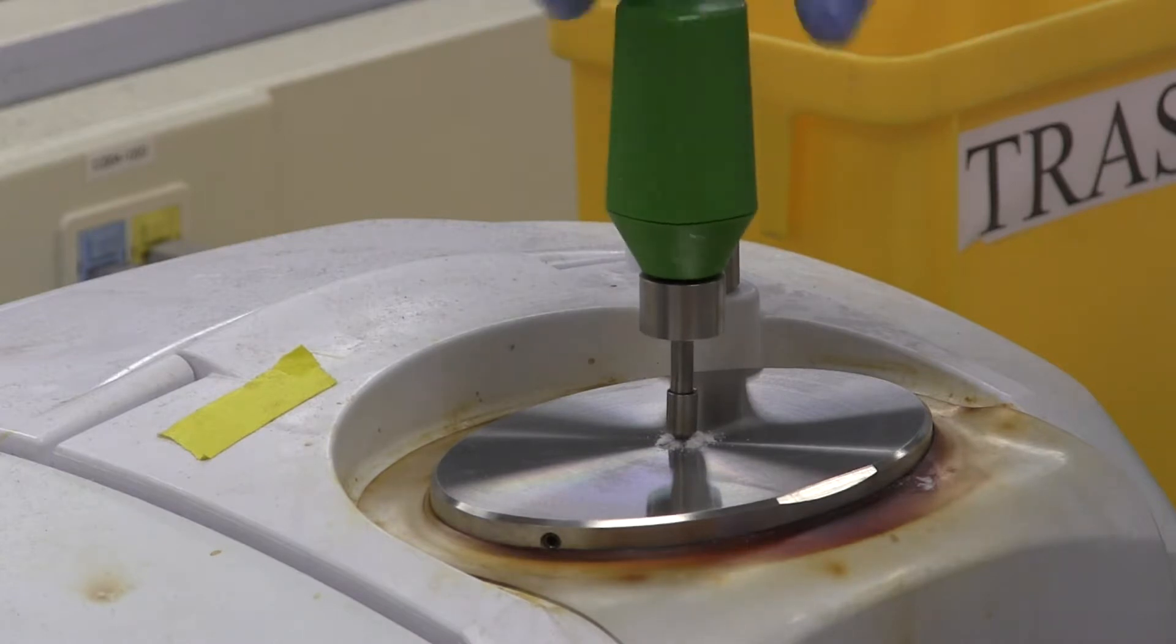You will recognize when the arm is tight enough by the fact that the knob will begin to rotate freely. This step is especially critical since you want the sample to absorb as much infrared radiation as possible.